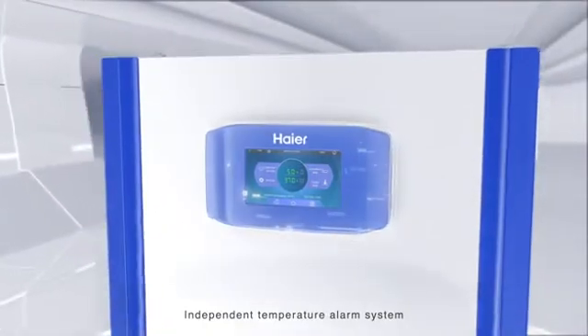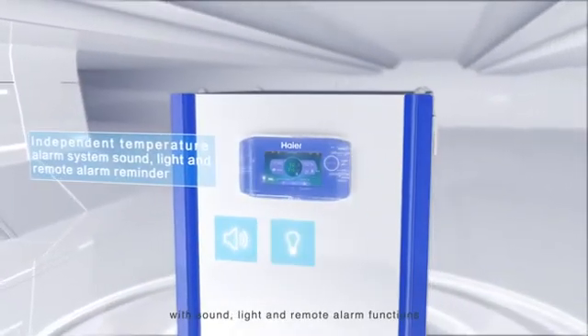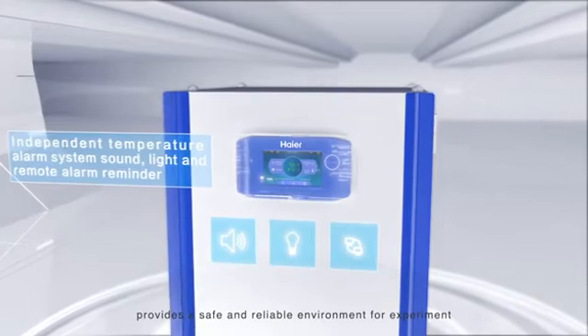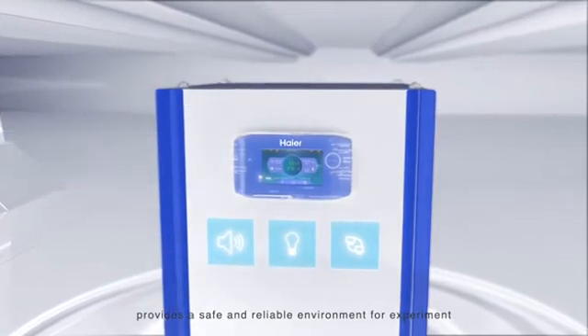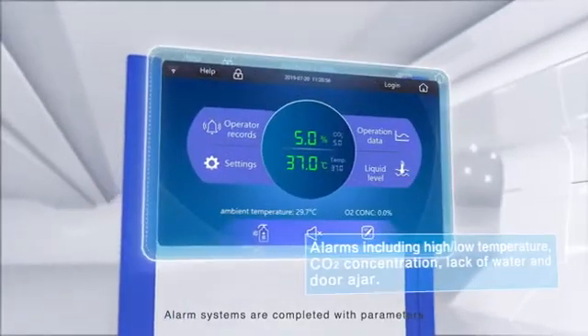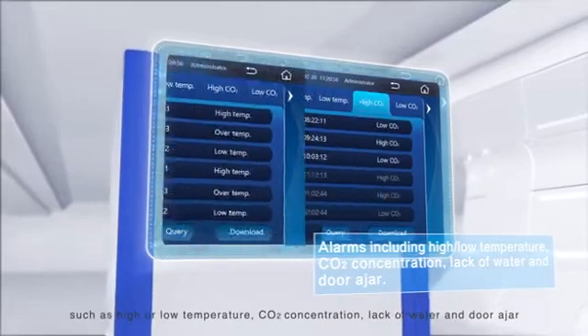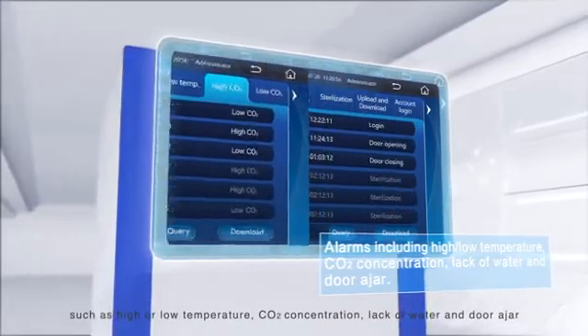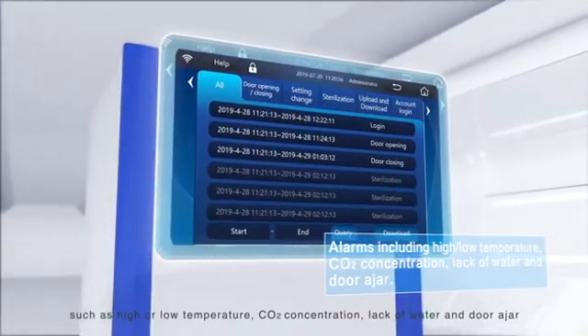Independent temperature alarm system with sound, light and remote alarm functions provides a safe and reliable environment for experiments. Alarm systems are completed with parameters such as high or low temperature, CO2 concentration, lack of water and door ajar.